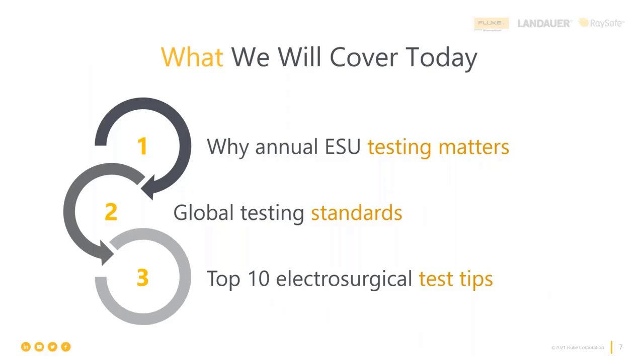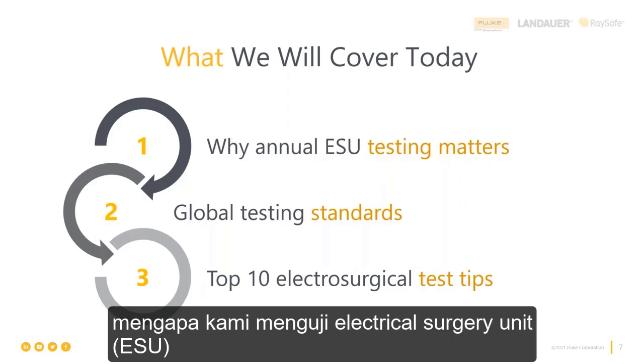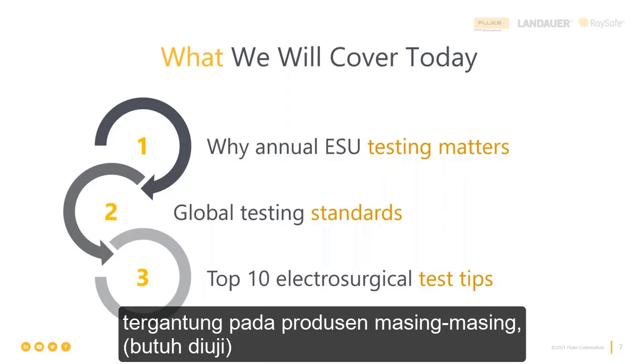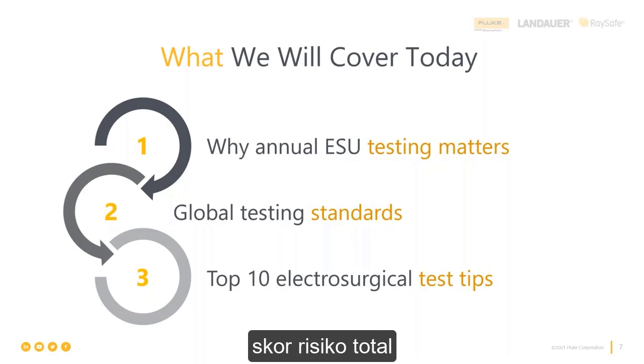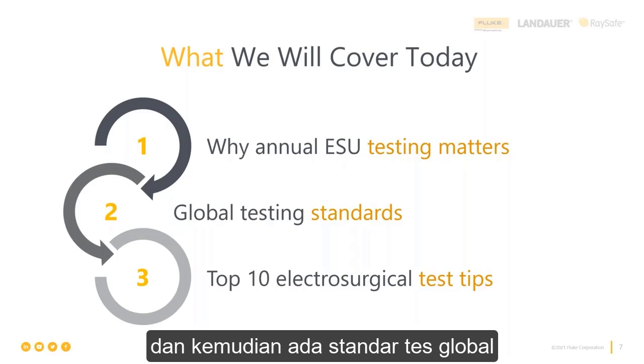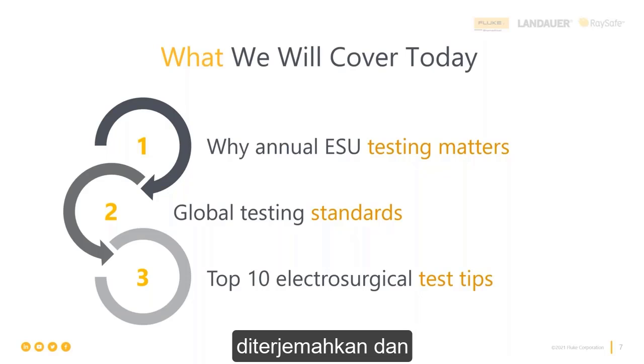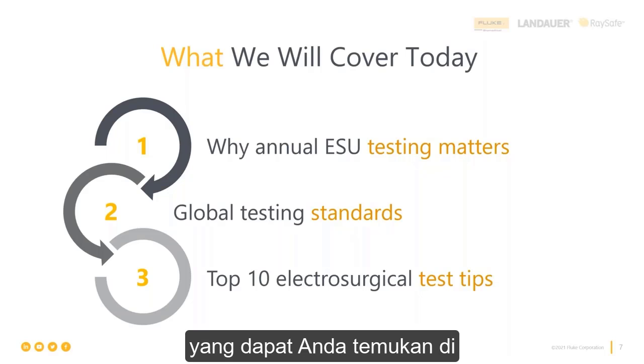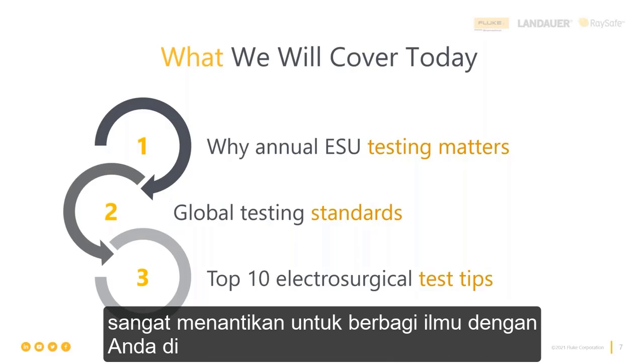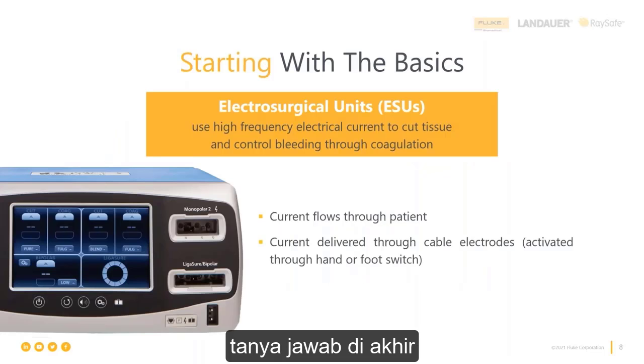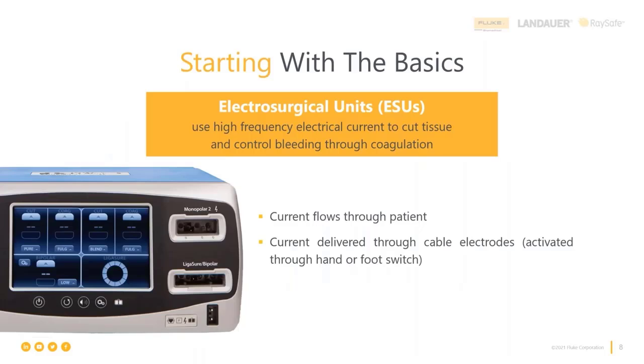We'll cover why we test electrosurgery units. Depending on the manufacturer, it's at least once per year, but many are twice per year, when you look at the total risk score that we use in a risk-based determination of how often to test. Then there are global test standards that get translated and integrated into the brand- and model-specific test procedure that you'll find in the service manual for your ESU. We'll talk about some electrosurgery unit testing tips, and we look forward to sharing with you in the Q&A at the end. So let's start with the basics of the electrosurgery unit.